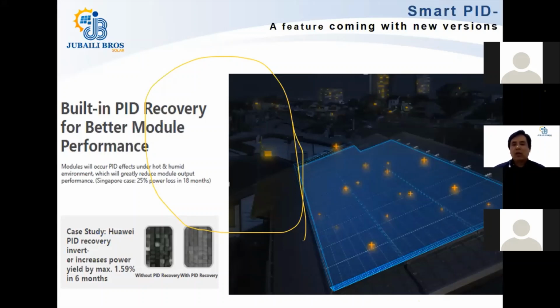So what Huawei is doing is building this feature into the new range of inverters, which will be soon available in the market. And the Huawei inverter at night time will use a very small amount of power from the grid to send pulses towards the solar PV modules, and the effect that the PID has on the solar modules will be eliminated. In this way, your PID will be recovered and it will not increase over time.